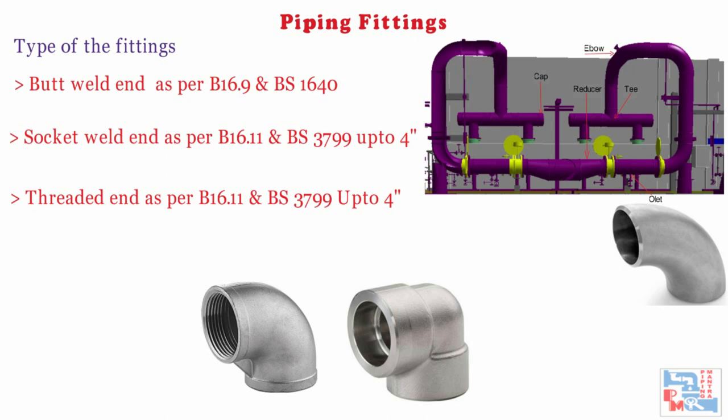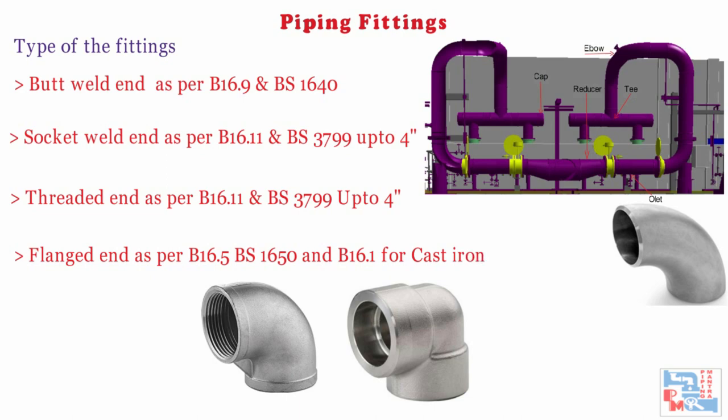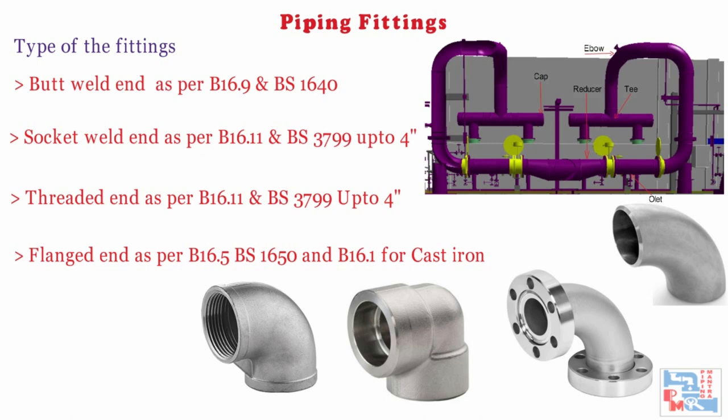For female threaded end fitting, the pipe should have a male threaded end. Flange end, as per ASME B16.5, BS1650, and ASME B16.1 for cast iron — pipes should have companion flanges. For example, for a raised face flange end, the pipe should have a raised face flange.